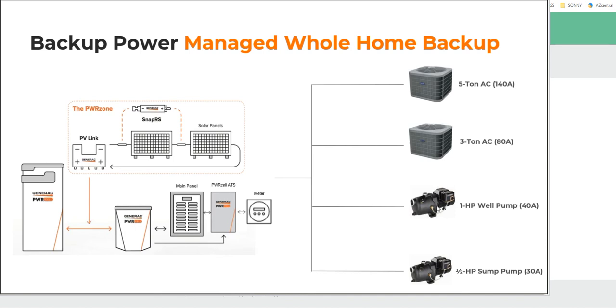But when the power goes out, we're willing to alternate running our pump with running our 3-ton air conditioner, so sometimes we have water when we need it, and also we're not melting in our house. So here's what happens: when the grid goes down, the sump pump gets power all the time. The well pump is set as priority 1 with one of our smart management modules, the air conditioner is set as priority 2, and lastly the big boy, the 5-ton air conditioner, is set on lockout.